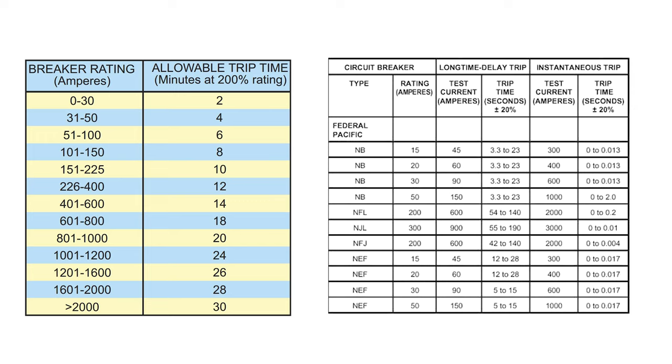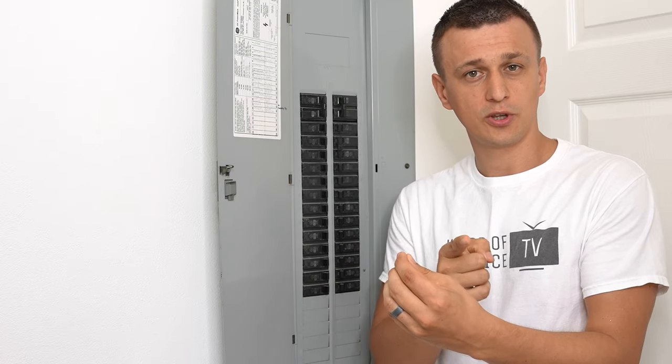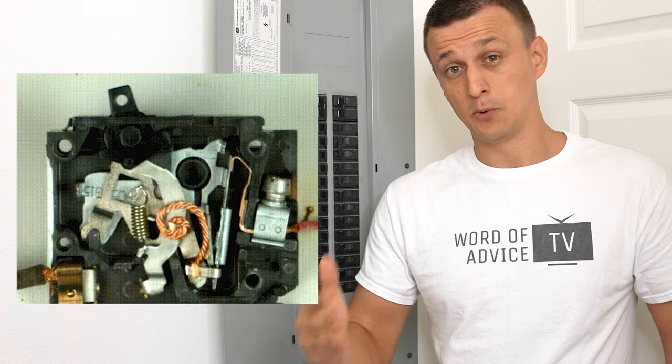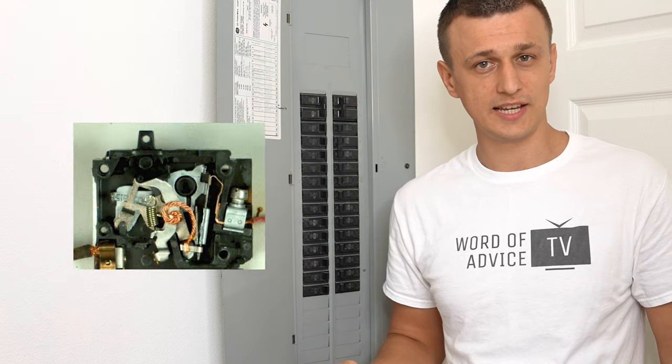In fact, here's a quick fact for you. Let's say we have a 20 amp breaker and there's 22 amps going through it. It might take it hours to trip. But of course, if there were 60 amps going through it, then it would trip in just a few seconds.